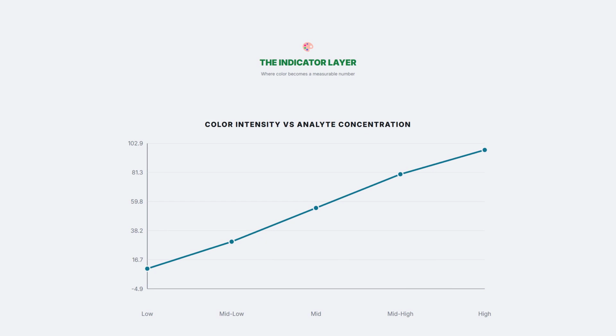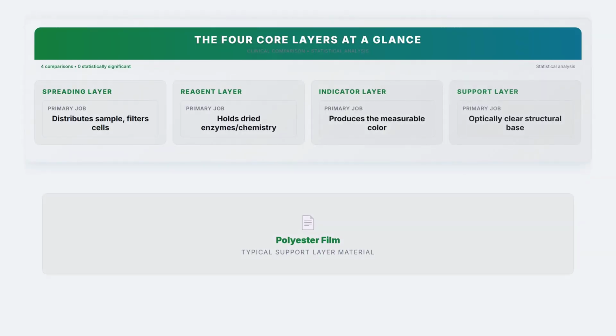The indicator layer, immediately beneath the reagent layer, is where the reaction's end product actually becomes visible and measurable. The dye or chromophore generated by the enzymatic reaction concentrates here, its color intensity directly proportional to how much analyte was present in the original sample. The support layer, the base of the whole structure, is optically clear and mechanically rigid, usually a polyester film, existing purely to give the laminate physical structure and, critically, to let the reflectance reader's light beam pass through cleanly to illuminate the indicator layer from behind.